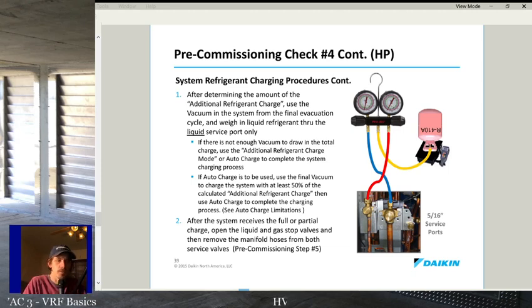You guys do what you want, but unless you've got a system that's holding 50-60 pounds of refrigerant or something, or I would say over 30. If you got a system that holds over 30 pounds and you don't have a recovery cylinder big enough for what you're doing, then I would not bother charging something in by weight.